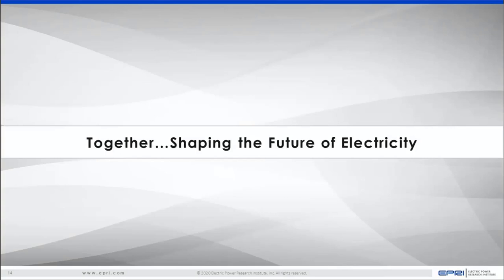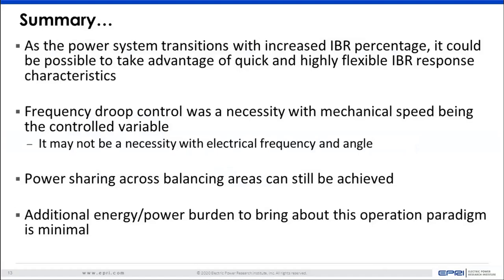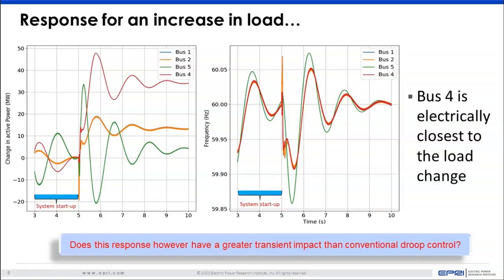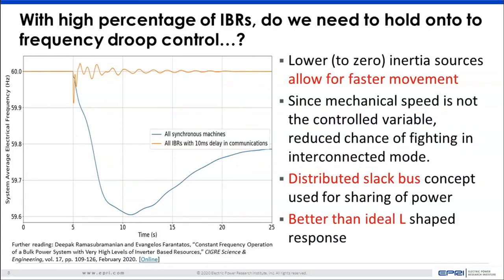Yeah, so we have a few scenarios. If I may just go back once. We don't have it in this particular slide, but the first plot that I had showed where there are 10 milliseconds of delay in communication. We also did a few sensitivity studies to look at the delay in sensing the frequency and the delay in communication between this variety of resources, going all the way from around 10 milliseconds to around 100 milliseconds, which is reasonable for a local frequency measurement, and how that impacts the performance and how the other controller gains depend on that delay. So I acknowledge that, yes, that has to be taken into consideration, and that is something we have done a little bit of work on, and we continue to do work on that.